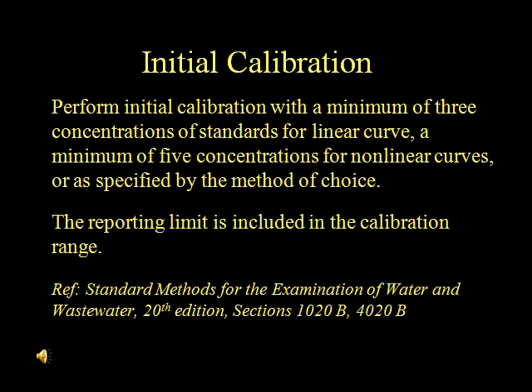There are some general guidelines as to the acceptable number of reference standards that are needed to perform a calibration. The first reference to use in determining the acceptable number of calibration standards is the specific method being used. However, if there is no specific criteria listed, then standard method states to perform initial calibration with a minimum of 3 concentrations of standards for linear curve, a minimum of 5 concentrations for nonlinear curves, or as specified by the method of choice. As we discuss some of the general guidelines, it is important to remember that the reporting limit is included in the calibration range, and if the reporting limit is not included, then a reporting limit verification standard should be analyzed.